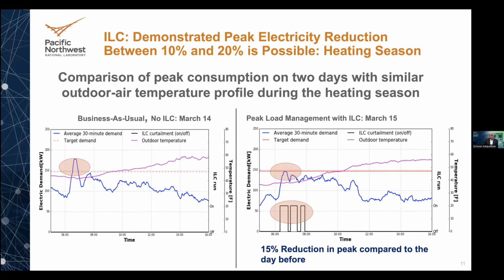Both graphs show electricity demand in blue on the left y-axis, and then outdoor temperature in purple on the right y-axis. Time is shown from 4 a.m. to 4 p.m. on the x-axis at the bottom. Note that outdoor temperatures are similar on both days, and the electricity demand that we're showing is a 30-minute rolling average. Because the building uses heat pumps with backup electric heat, the peak demand of 175 kW on the first day on the left was set around 7 a.m. in the morning. And note that the rest of the day, the demand never exceeded 145 kW. Also note that the duration of the peak was probably less than 15 minutes.